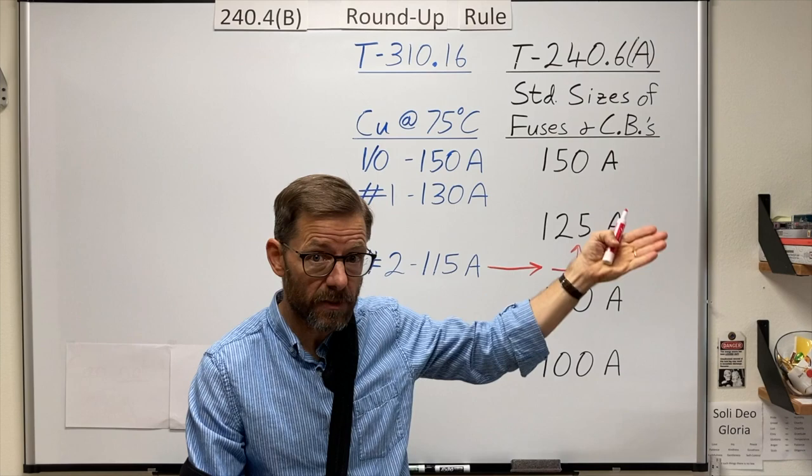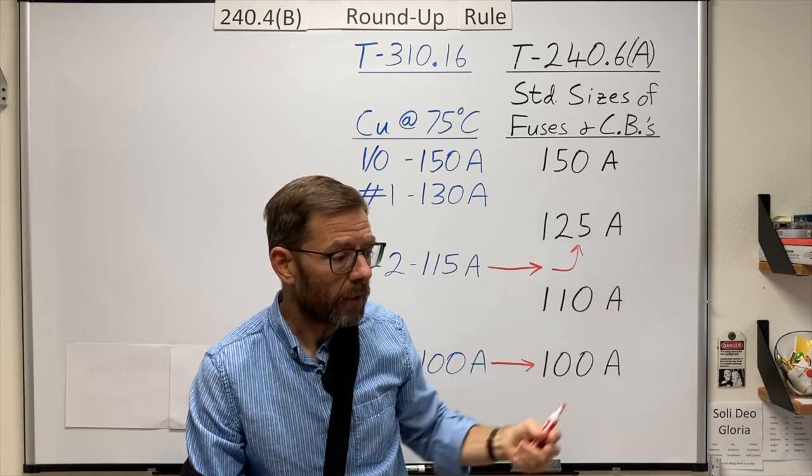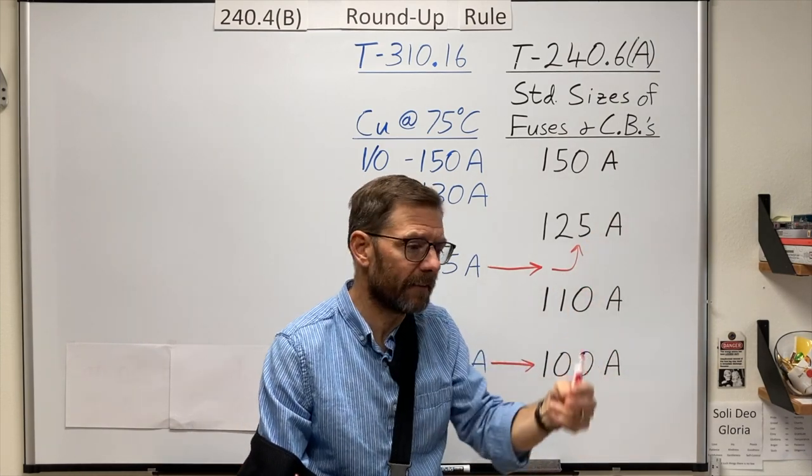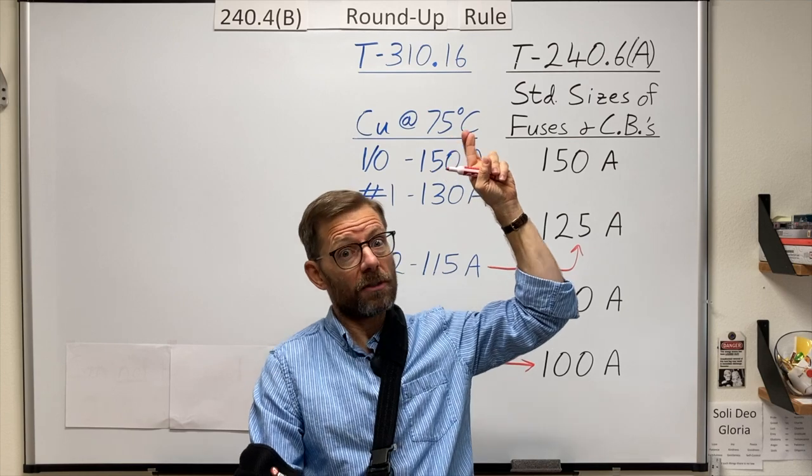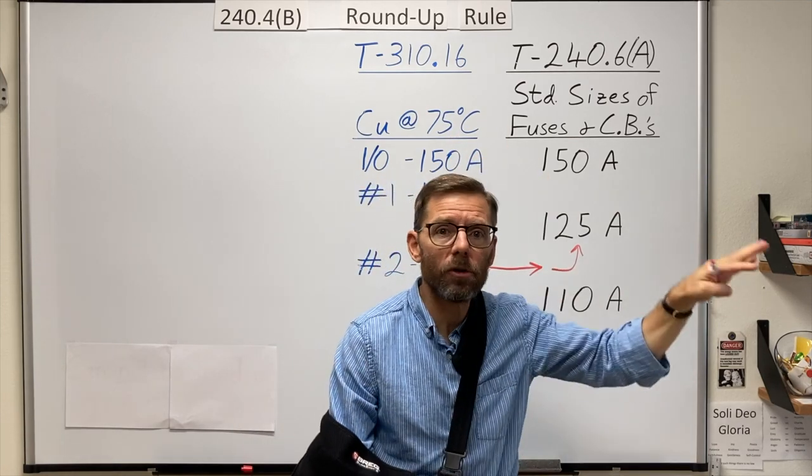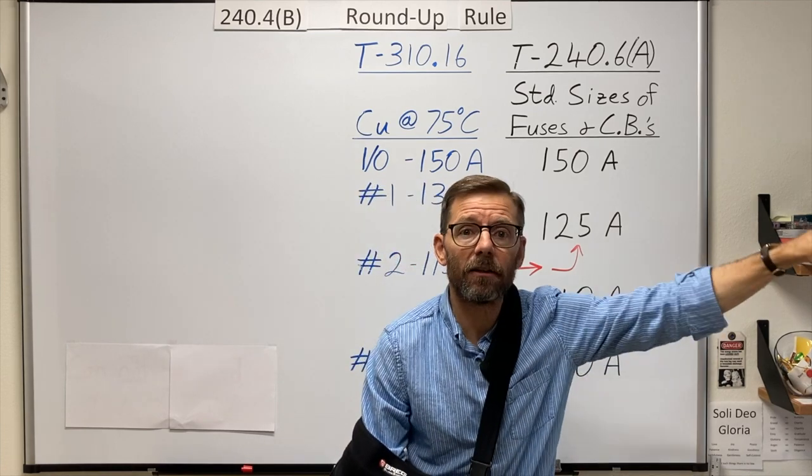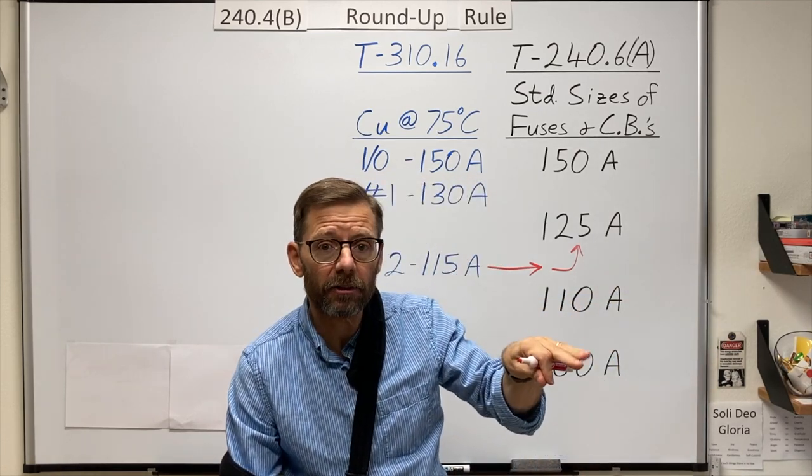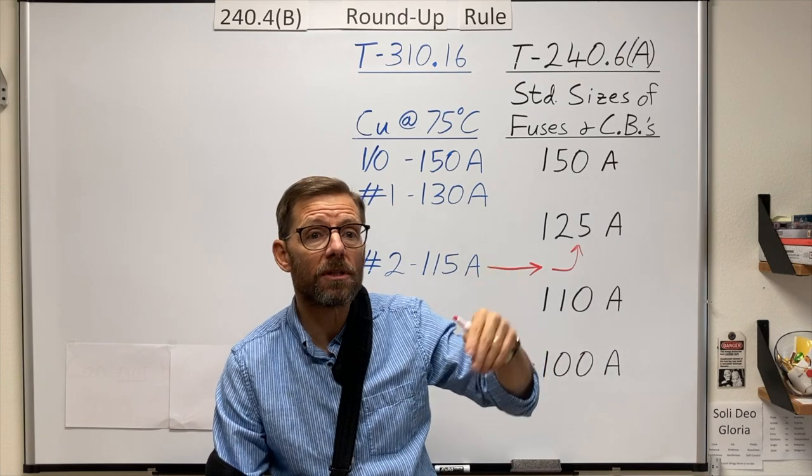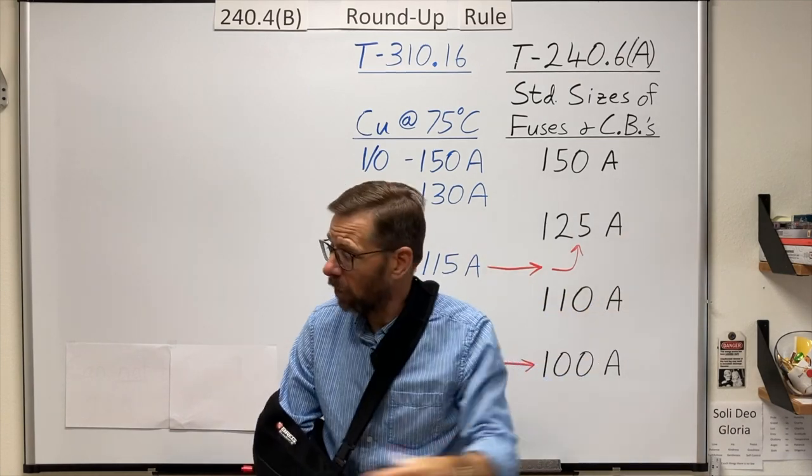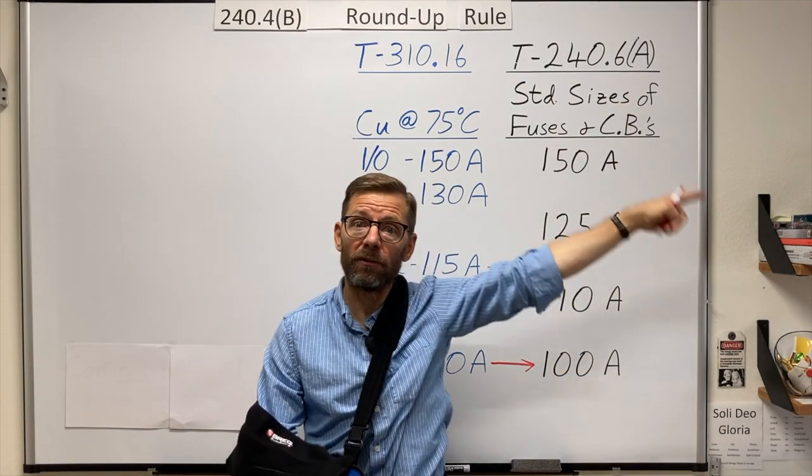And if I go into an existing facility to add a load, I don't just find the closest circuit, connect it up, cross my fingers, hope it works. No. I analyze the whole circuit, from overcurrent device, to conductor, to connected loads, to see if there is room on that conductor to add some more amps for the new load, or do I need to run a new circuit out there for it?